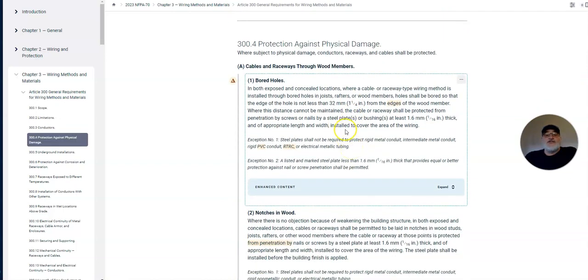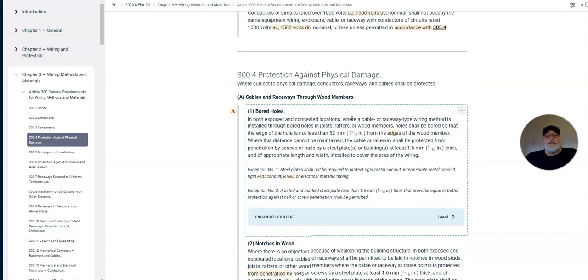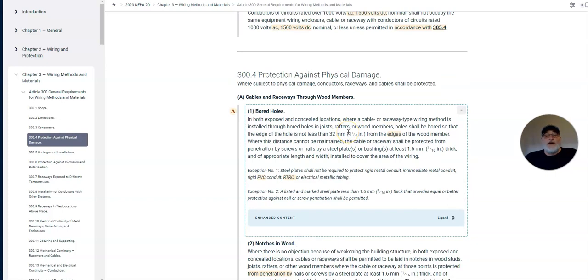Let's look at protection against physical damage. It's very important that we understand protection against physical damage. Where subject to physical damage, Conductors, raceways, and cables shall be protected. So let's look at this. We're in a residential stick build, which is wood, 2x4, your standard house. You have to drill holes in the wood to be able to get from your box up into the ceiling or up from the next box down the wall.